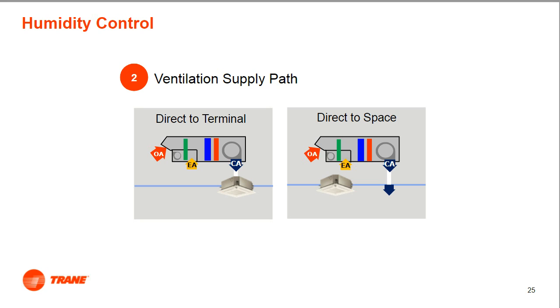There's also the direct-to-space configuration. One of the advantages of the direct-to-space method is that it helps to ensure that the required outdoor airflow reaches each zone. As a byproduct of this method, VRF terminal fan coil units do not need to be operating in order to distribute air. This method also allows the dedicated outside air system to operate during unoccupied periods. It also provides the opportunity to downsize VRF terminals if colder conditioned outside air is to be used. Conversely, the disadvantage of this method of delivery is mainly due to the additional ductwork and diffusers needed for first costs.